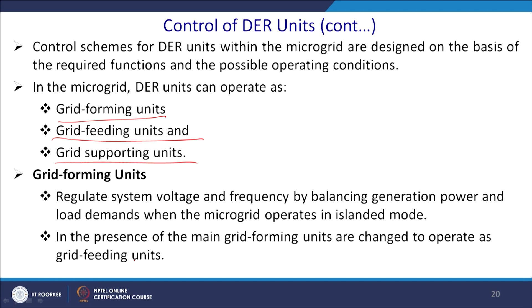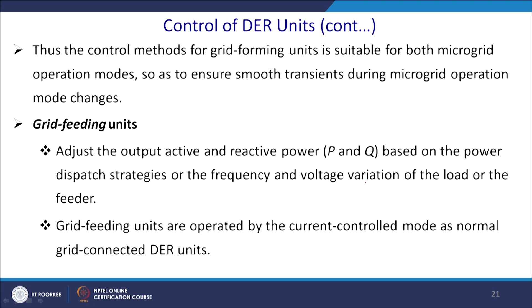Another mode is the grid feeding mode, which adjusts the output active and reactive power based on the power dispatch strategies that we have explained in equation numbers 4 and 5, according to the frequency and voltage variation in the load or the feeder. Grid feeding units are operated by the current control mode, as normal grid connected DER units.